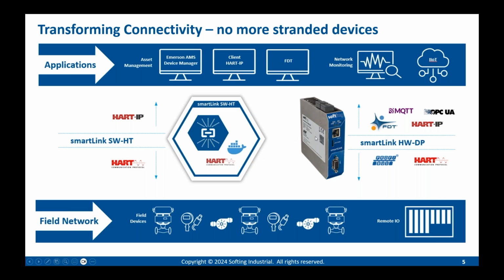On the right side, just to highlight, for the older technology, that is Profibus DP, you have your HART devices connected to Profibus remote IOs. This SmartLink hardware can provide you access to the Profibus DP segment, and then through HART IP, FDT, MQTT, or OPC UA, you can send it northbound to AMS Device Manager, to the cloud, to network monitoring, or any other kind of application.